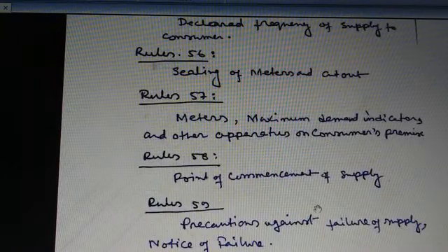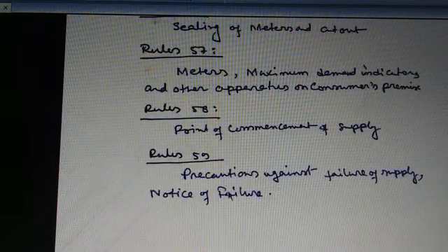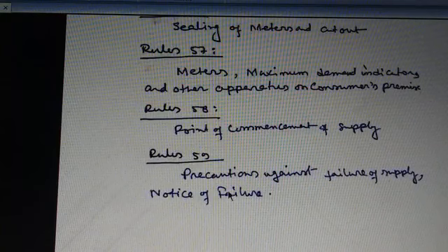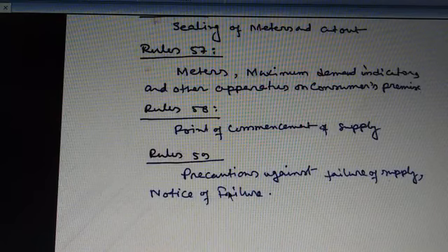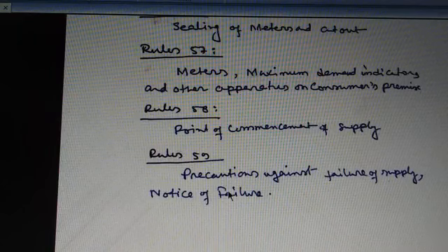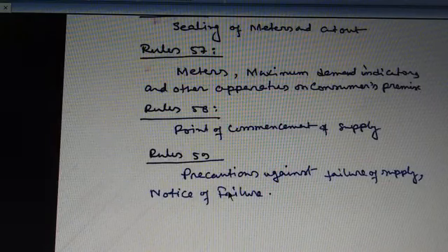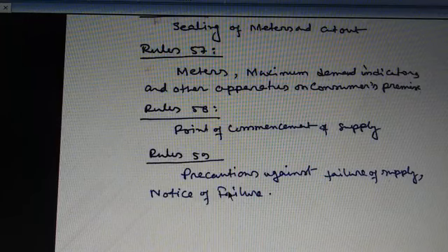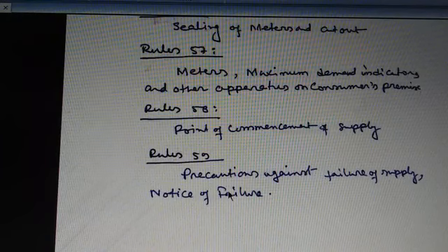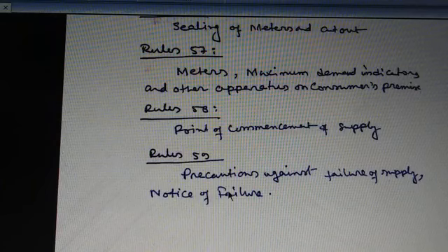Next, rule number 59. Precautions against the failure of supply. Notice of failure. The layout of the electric supply line of the supplier for the supply of energy throughout his area of supply shall, under normal working condition, be sectionalized and so arranged and provided with cutouts or circuit breakers so located as to limit the extent of the portion of the system affected by any failure of supply.